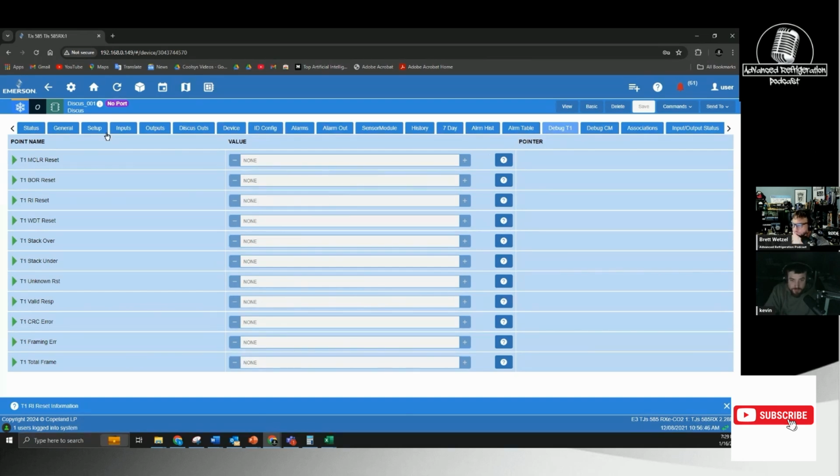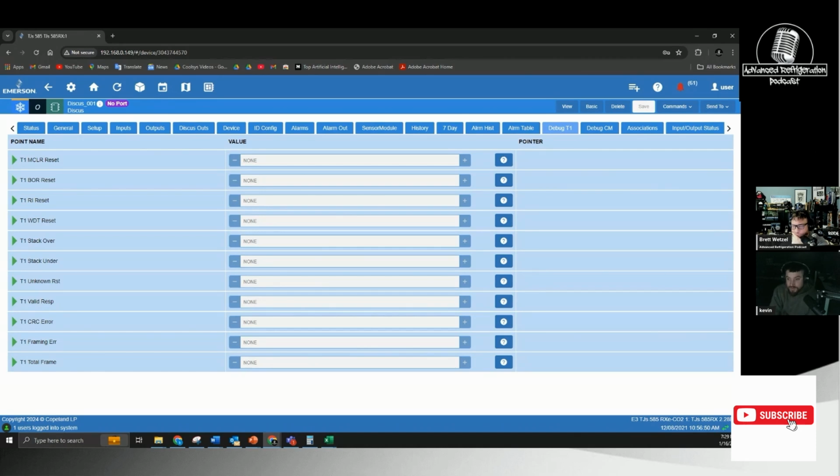So it is nice having that on there and having the discharge temp. But you also have to remember the discharge temps are actual compressor discharge temps. They aren't line temps. Your line temps are going to be lower. The lockout may be like 310 on those, but you're going to lose like 60, 70 degrees. It's measuring the inner head temp. So your line temps are going to be 60, 70 degrees less. So if it's reading 250, 260 on the controller, it's like 200 degrees. That's not great, but it's not horrible for CO2.